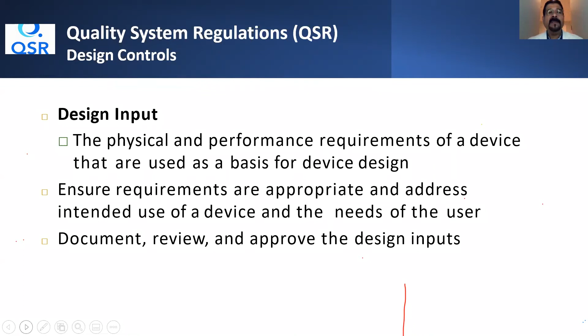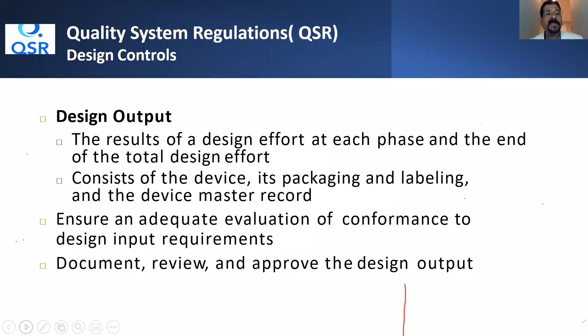So for example, you are designing an auto injector. The moment you press it against the skin, the needle should automatically be released, deliver the product, and then retract. That should be your design input requirement. Now for that, your design output will be the gauge of the needle, the size of the needle, the penetration time, the transition time of the needle to your skin, the depth of penetration, the plunger force which gets automatically activated. Those become part of your design output. Then you document all these things and approve the design output.